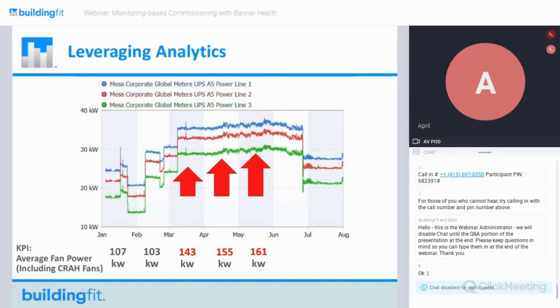If you look at the KPI at the bottom, this is the KPI after we included the fan powers from all those little fans. You can see in March, all of a sudden, that huge jump of 40 kW. It turned out that these CRAH units had a programming error that caused half of the fans to jump to 100%.